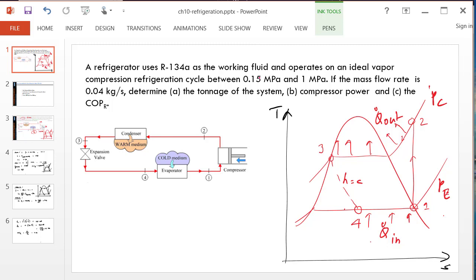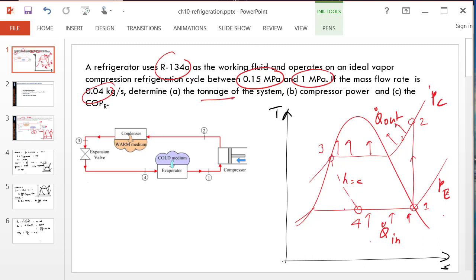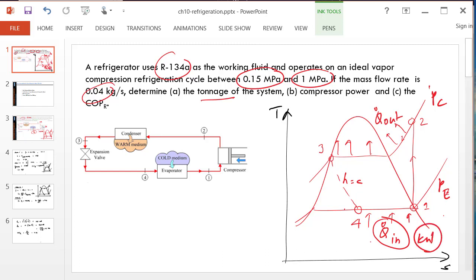The evaporator pressure is supplied, the condenser pressure is supplied, the fluid is R134A, and the mass flow rate is known. We are asked to find the tonnage of the system — that is, Q dot in in the specific unit of a ton of refrigeration. Q dot in should be in kilowatt, and it's just a conversion from kilowatt to tonnage. A ton is about 3.51 kilowatt.